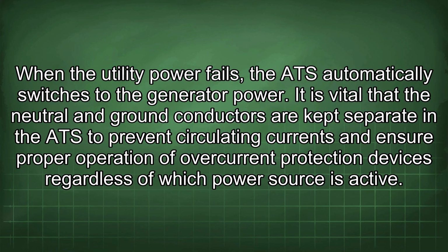It is vital that the neutral and ground conductors are kept separate in the ATS to prevent circulating currents and ensure proper operation of overcurrent protection devices regardless of which power source is active.